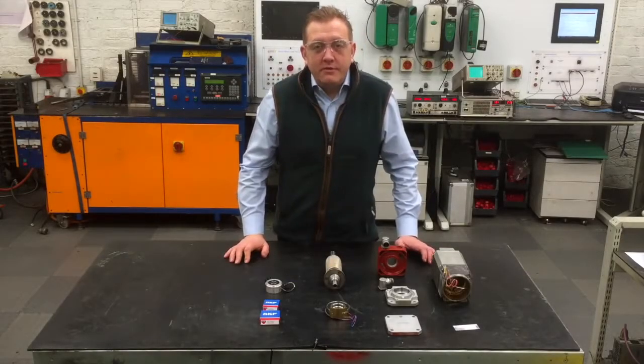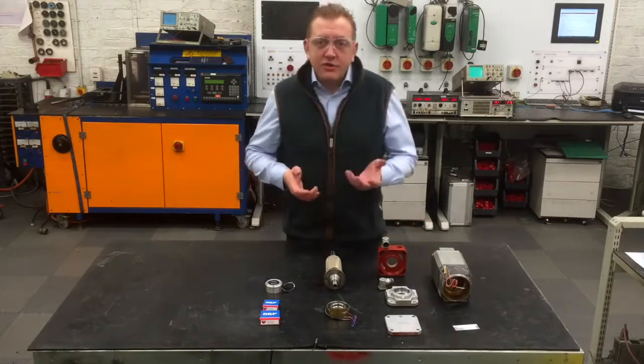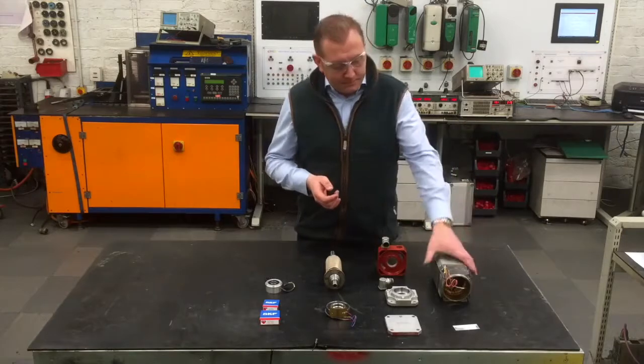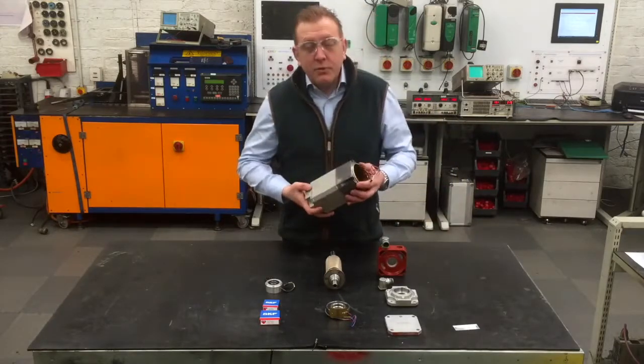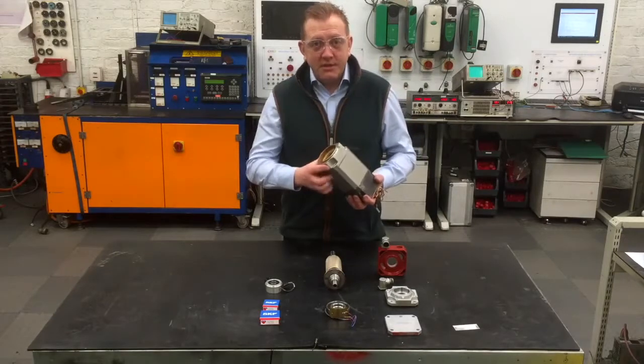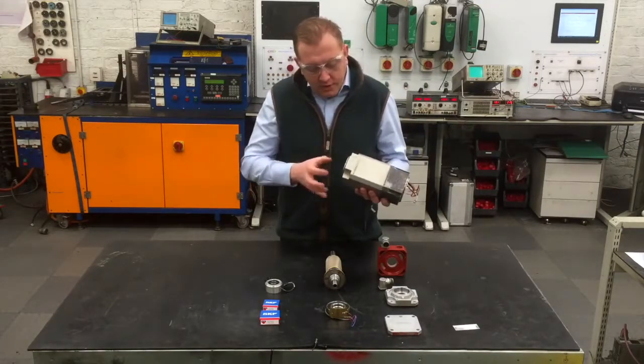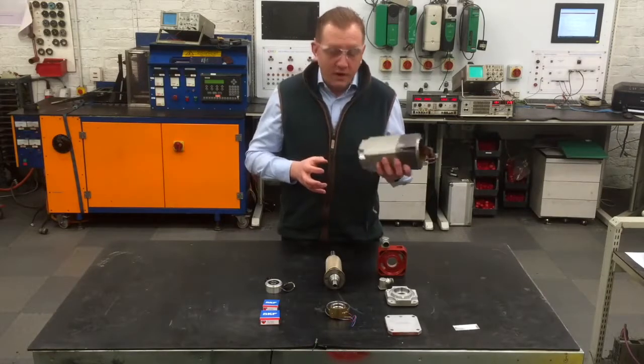All the parts of this Siemens servomotor have now been overhauled, so we are in a position now to assemble the motor. And just to recap what we have done to this point. The motor windings have been resistance checked, insulation resistance checked, high potential tested, and surge tested. So we know they are all good. We have also varnished the windings as well so they will last.